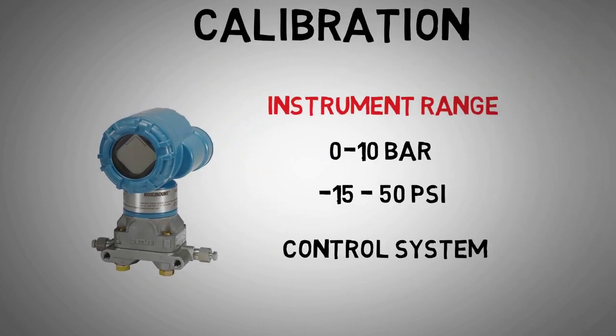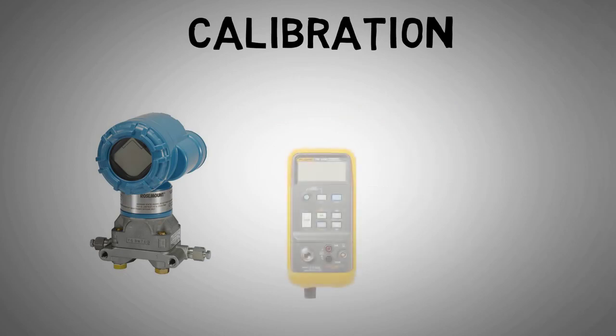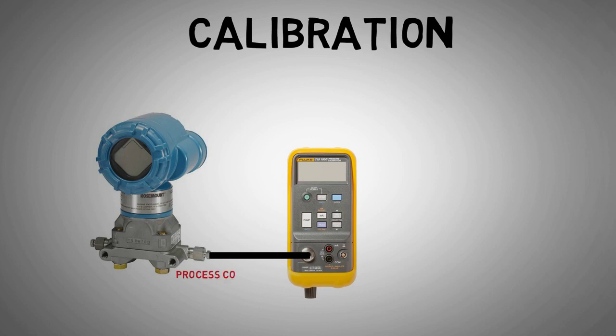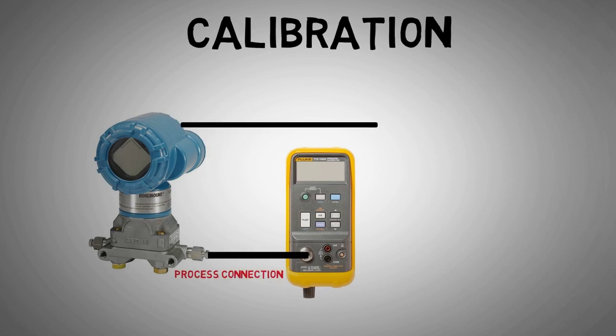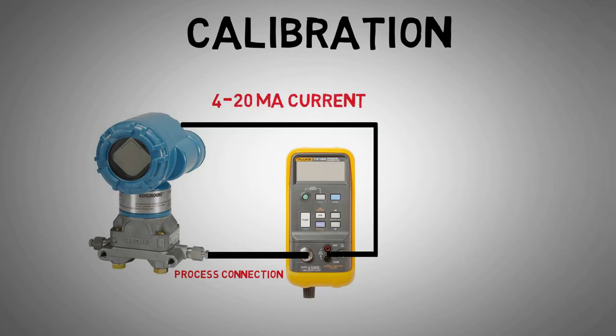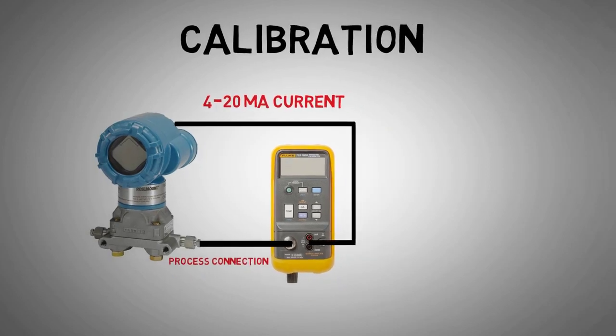We would then connect a calibrated, suitably ranged pressure pump or calibrator to our instrument via its process connection. We would also connect the transmitter electrically to a calibrator to test the 4 to 20 mA current signal that the transmitter gives out to different inputs. This is what the control system is converting to a reading for our process operator.